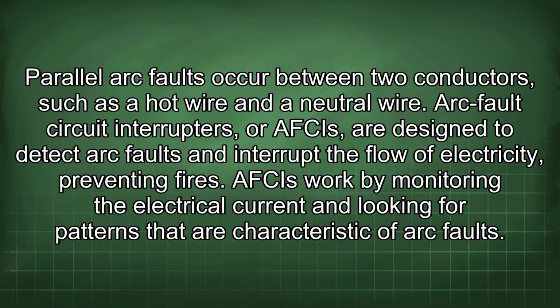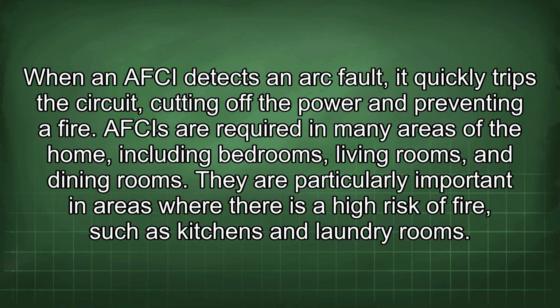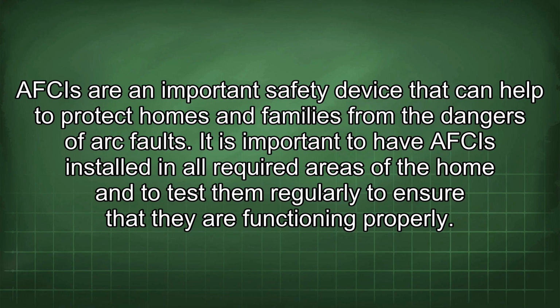Arc fault circuit interrupters, or AFCIs, are designed to detect arc faults and interrupt the flow of electricity, preventing fires. AFCIs work by monitoring the electrical current and looking for patterns that are characteristic of arc faults. When an AFCI detects an arc fault, it quickly trips the circuit, cutting off the power and preventing a fire. AFCIs are required in many areas of the home, including bedrooms, living rooms, and dining rooms. They are particularly important in areas where there is a high risk of fire, such as kitchens and laundry rooms. AFCIs are an important safety device that can help to protect homes and families from the dangers of arc faults.